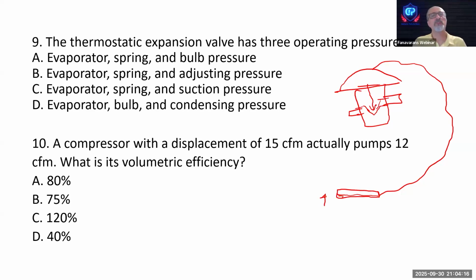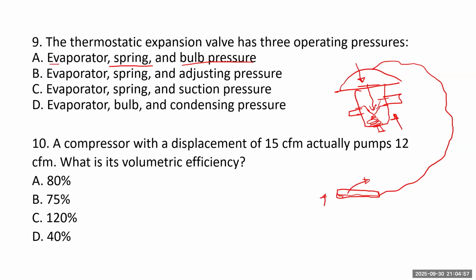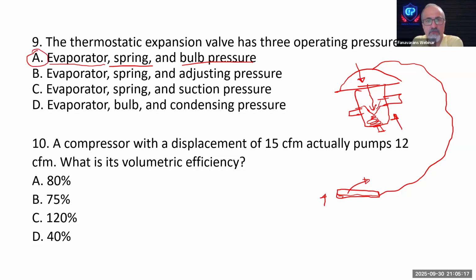So how many pressures do we have in the TX valve? Below it, we have a spring, connected to the stem, and it's adjustable. So there is a pressure below this needle, and the spring puts force opposite to the diaphragm, opposite to the pressure of the bulb. So we have the bulb pressure, the spring pressure. What else? We have the evaporator pressure. So the answer is A. I have good stuff for the TX valve, and it has at least 4 or 5 questions.